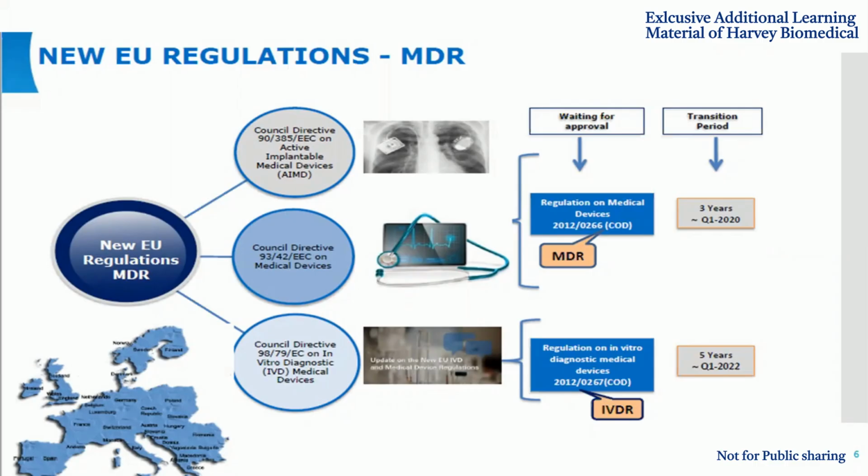If you see the medical device MDD to MDR, the transition period they gave was 3 years. Earlier it was May 26, 2020 as the transition date, but during this pandemic situation they could not manage. They planned 3 years for medical devices and 5 years for IVD devices.